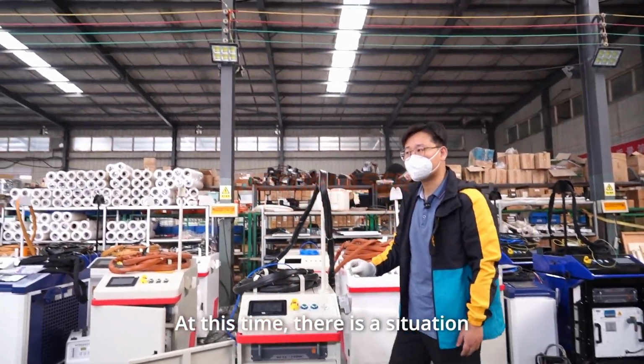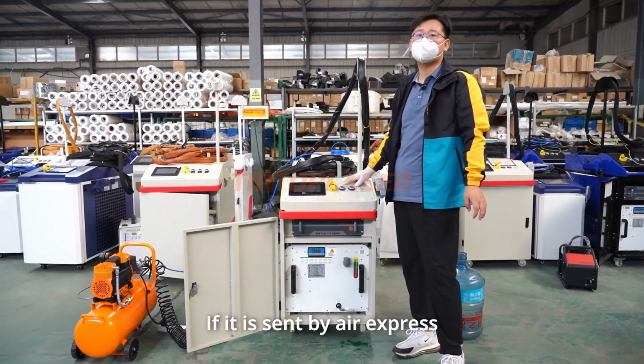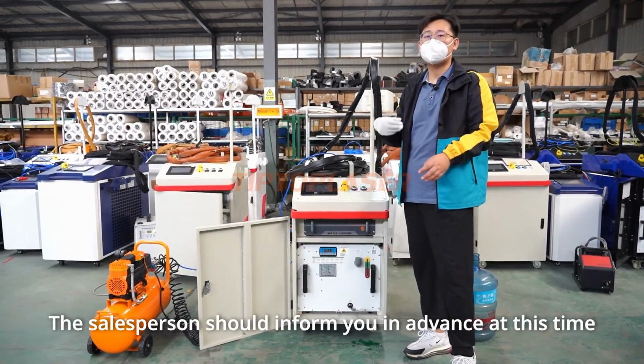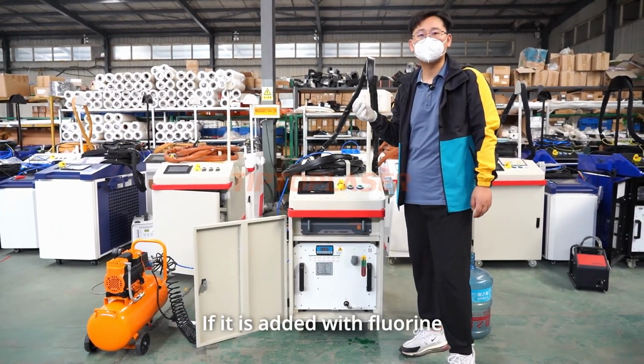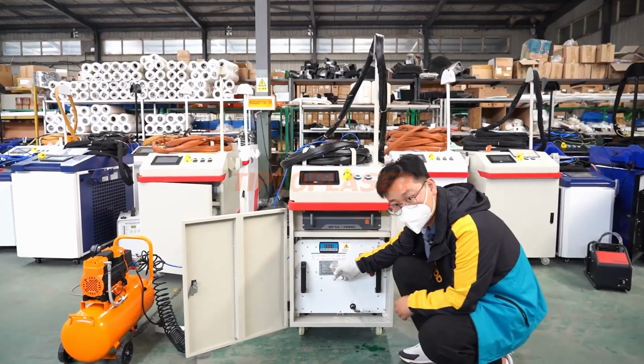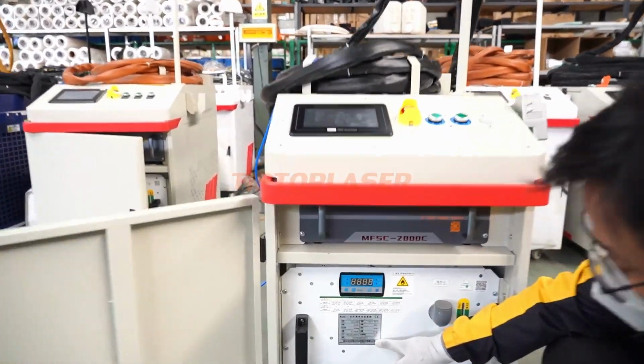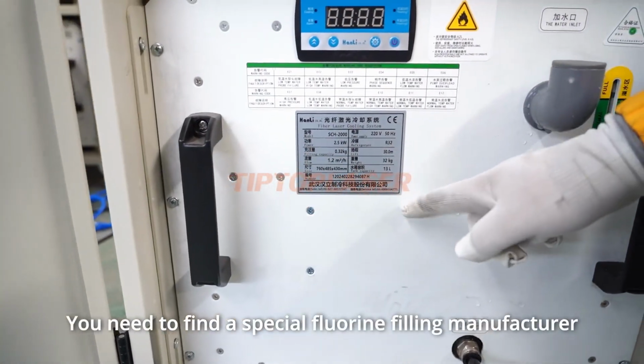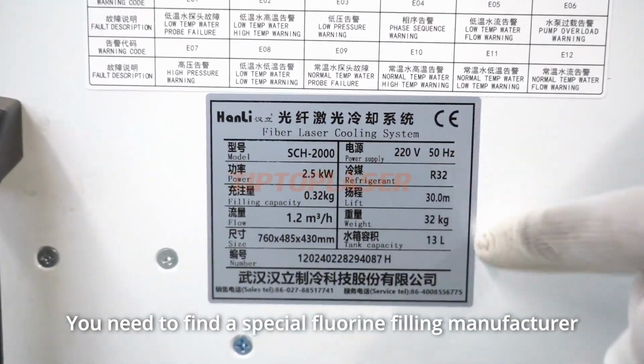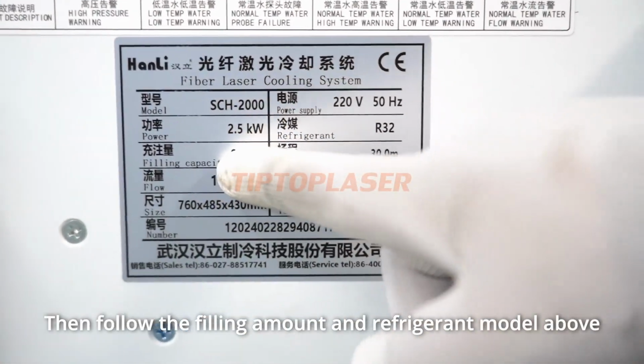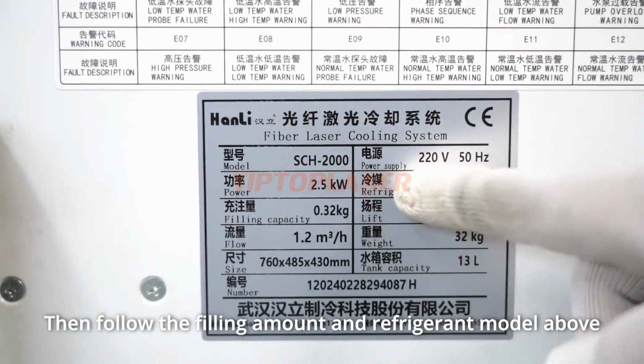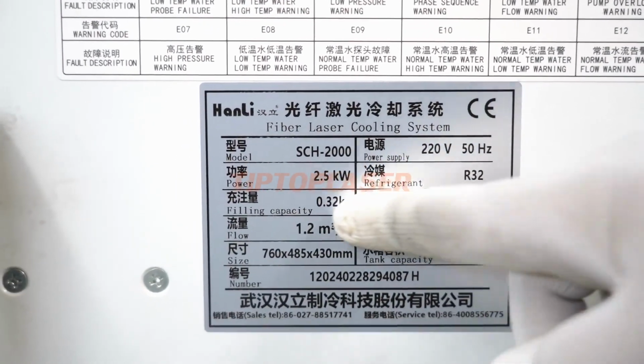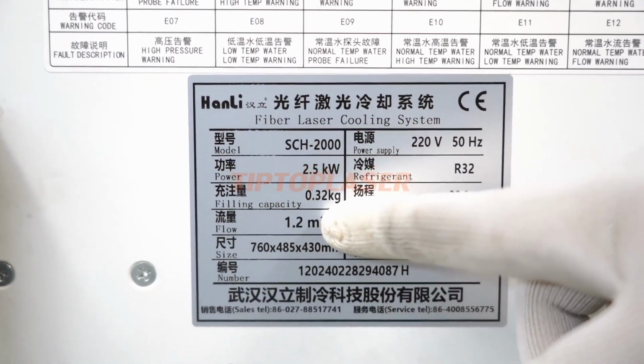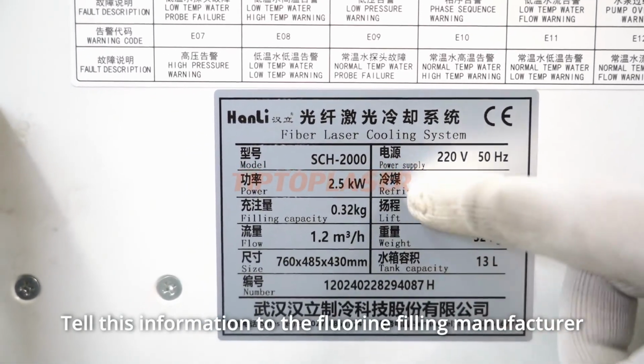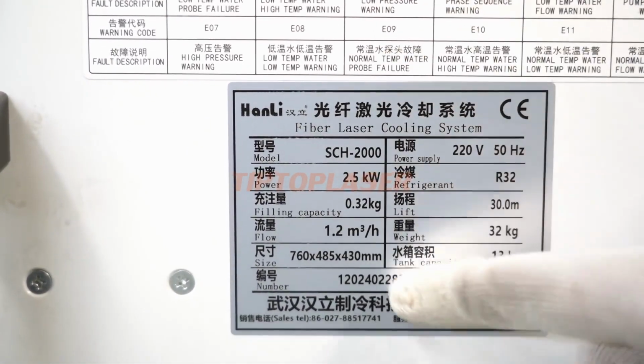At this time, there is a situation. If it is sent by Air Express, it may be possible to add fluorine. The salesperson should inform you in advance if it is added with fluorine. You need to find the special fluorine filling manufacturer. Then follow the filling amount and refrigerant model above. For example, this machine is R32. The filling amount is 0.32 kg. Tell this information to the fluorine filling manufacturer. Let them help you fill.